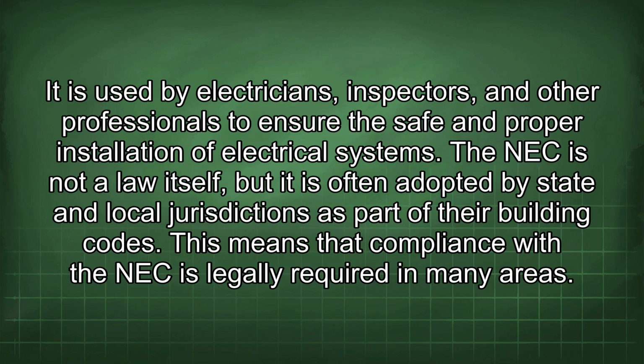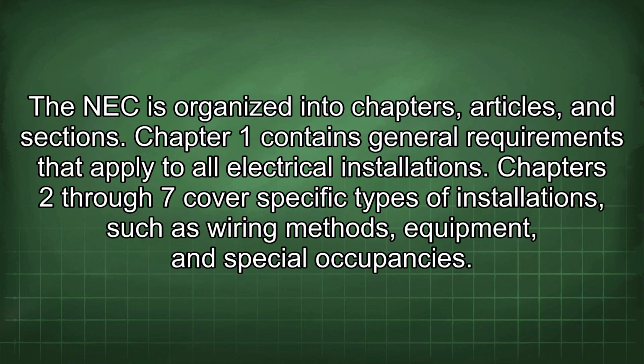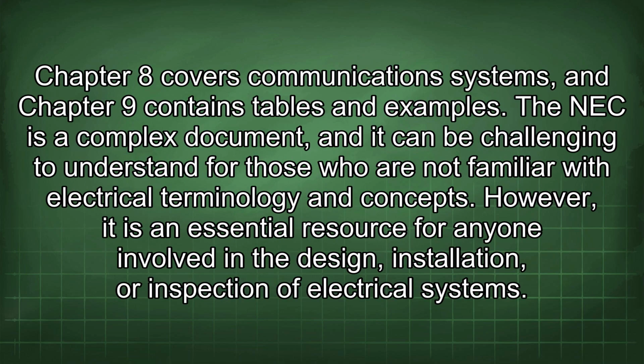The NEC is not a law itself, but it is often adopted by state and local jurisdictions as part of their building codes. This means that compliance with the NEC is legally required in many areas. The NEC is organized into chapters, articles, and sections. Chapter 1 contains general requirements that apply to all electrical installations. Chapters 2 through 7 cover specific types of installations, such as wiring methods, equipment, and special occupancies. Chapter 8 covers communications systems, and Chapter 9 contains tables and examples.